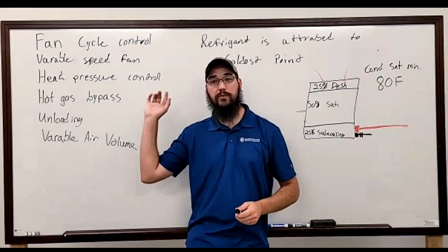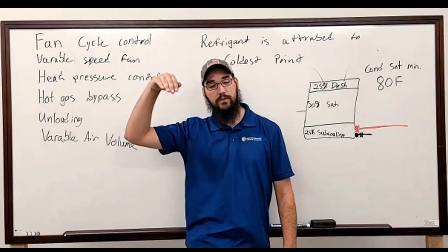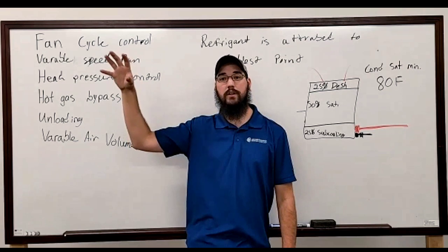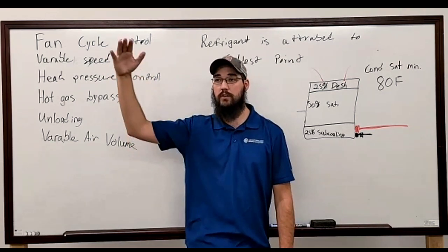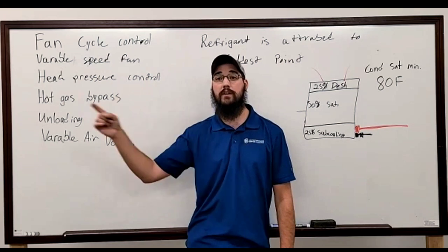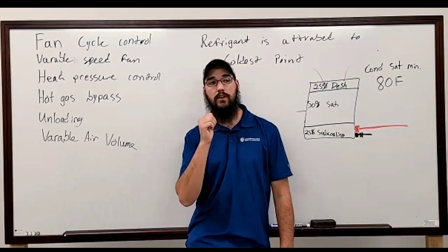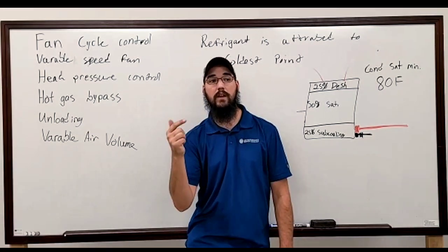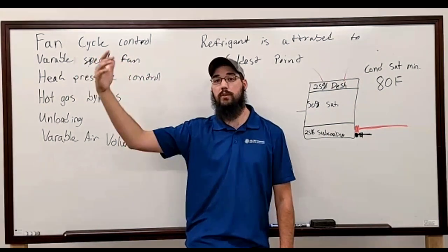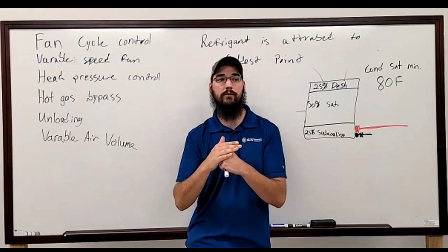And then there'll be a separate logic loop for the fans, and their main focus is to control the head pressure. So once the compressor begins to ramp down as it unloads, and we begin to drop in head pressure, the logic running the fan motors will respond to the head pressure drop and start ramping the fans down. The compressor is not controlling head pressure at that point; the fans are. Now, there are safeties built into the compressor logic: if it sees either amperage or head pressure start to exceed limits, it will limit that compressor's ability to go beyond a certain point, because it doesn't want to go into a safety or a negative condition. So it's not that there's no interaction at all, but it's only at a safety level.